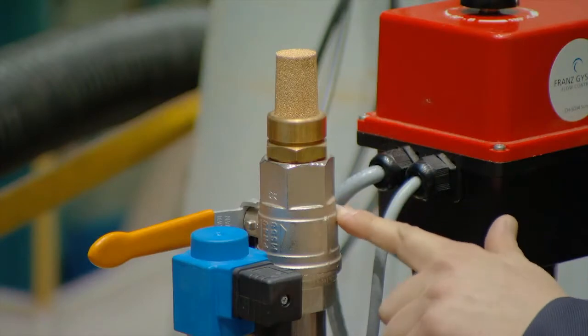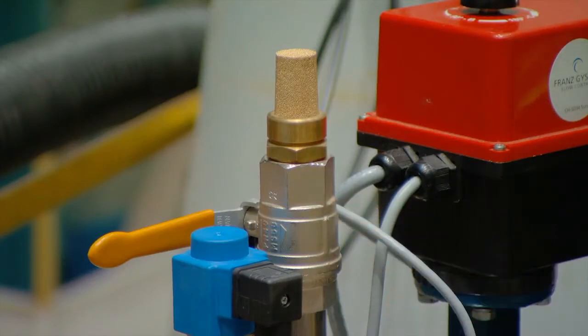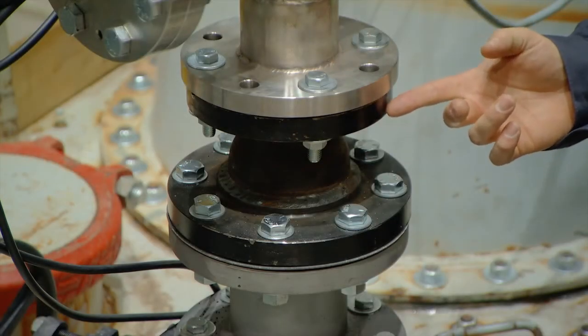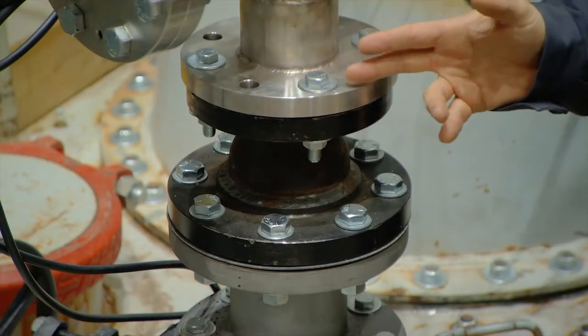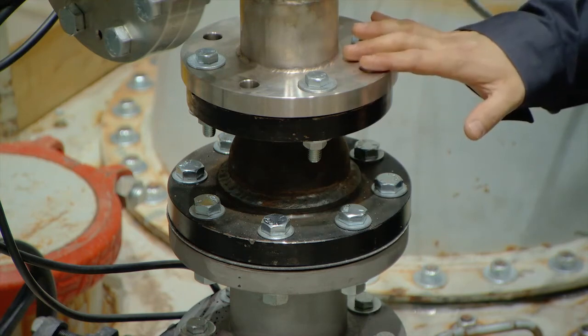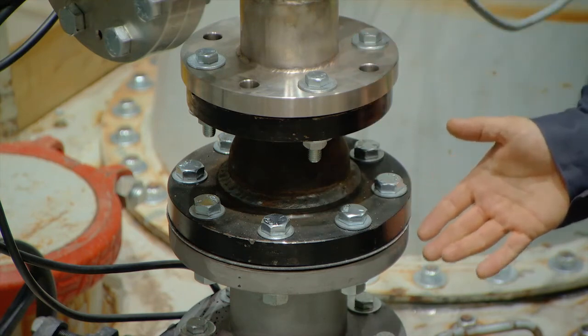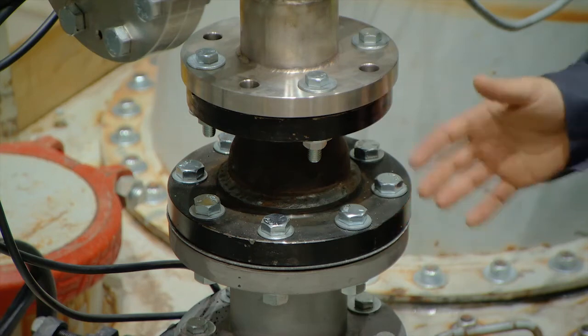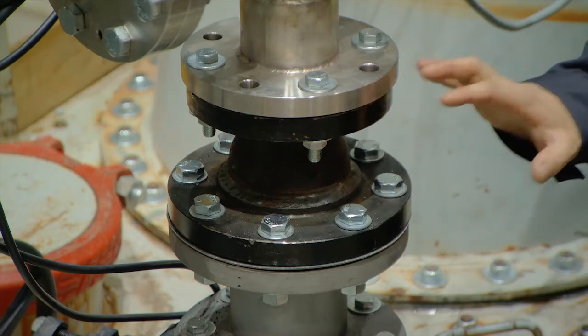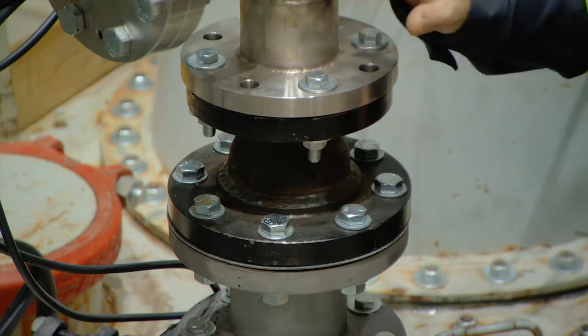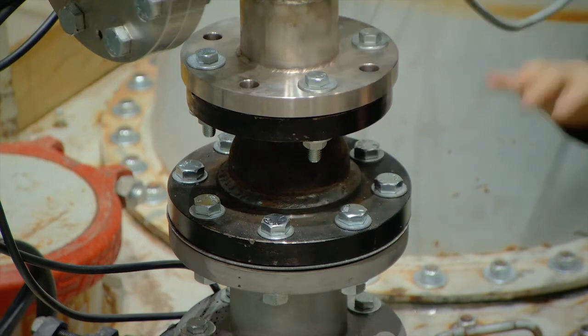This valve here in the middle is a manual aeration valve. It can also be used to aerate the transformer, but if you are going to use this valve, I do suggest connecting the dry air line to it. Here we have an adapter flange, which is used to go from a European style of flange to our American styles of flange. Very important to have this piece. Without this piece, you will not be able to connect the vacuum valve assembly to the transformer.